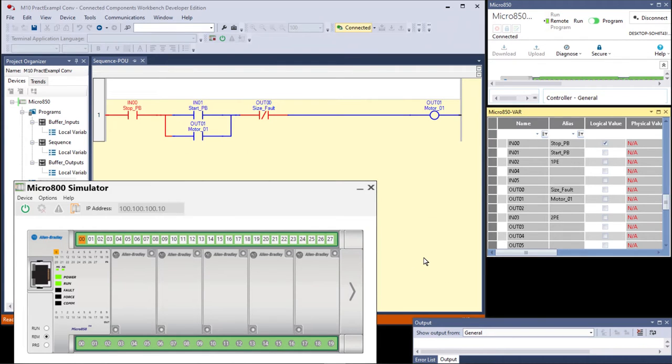So here's our standard stop-start circuit. And we have two things that can stop the motor, a size fault or a stop bit. So at rest, the conditions that are true are the ones that will interrupt it to release it. So if we want to start it, and you need to get into practice with the simulator as double-clicking. So I'm going to double-click on 1. You didn't even see it come on the screen. If you want to click slower so you can see input 01 come on the start push button, you can do that. Okay, the motor's running.